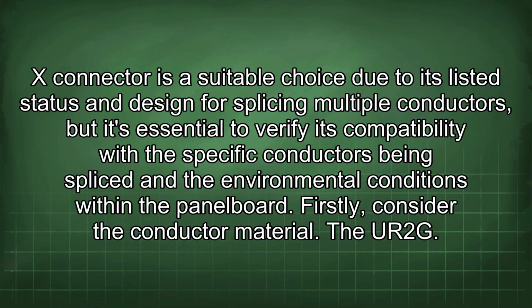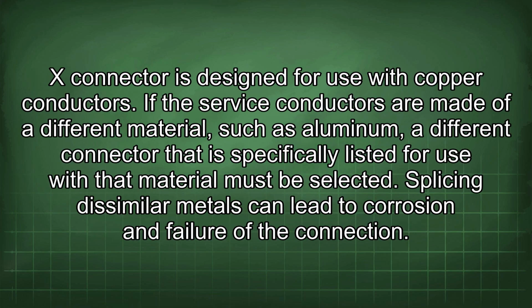the panel board. Firstly, consider the conductor material. The UR2G X connector is designed for use with copper conductors. If the service conductors are made of a different material, such as aluminum, a different connector that is specifically listed for use with that material must be selected. Splicing dissimilar metals can lead to corrosion and failure of the connection.